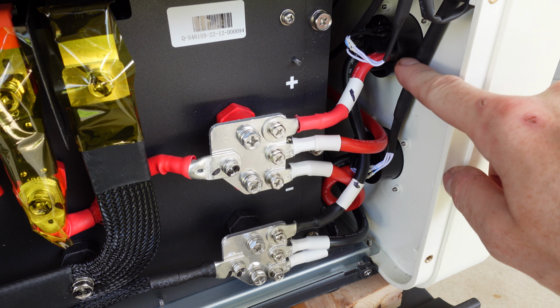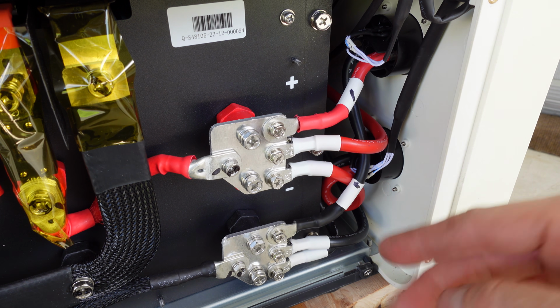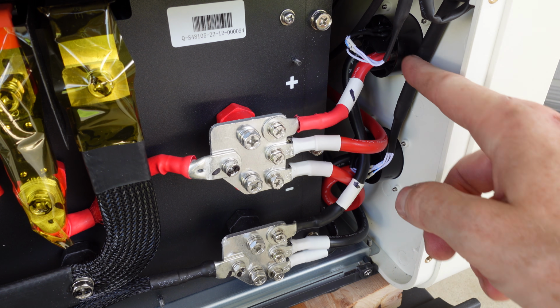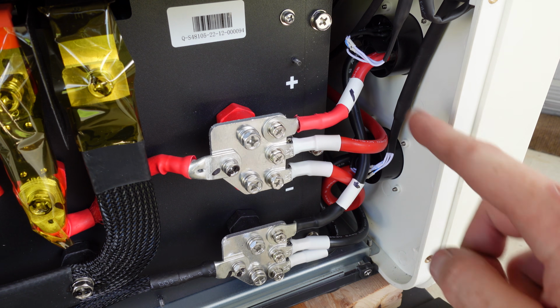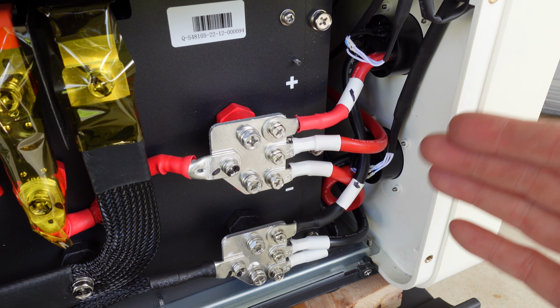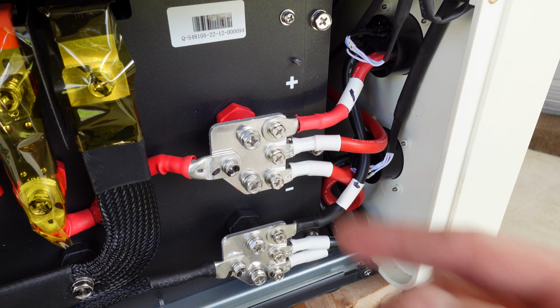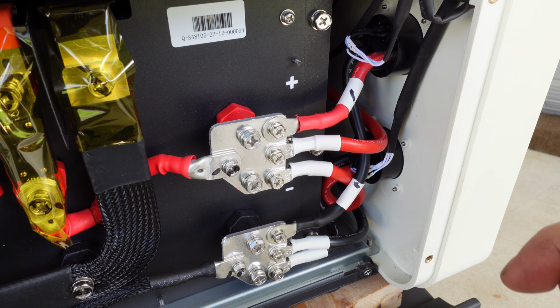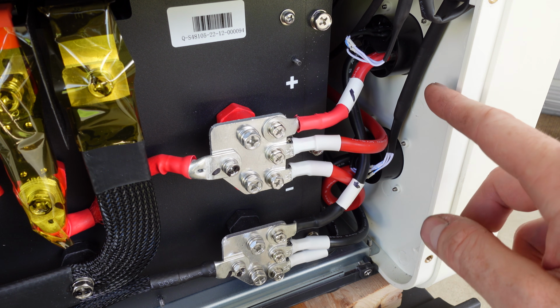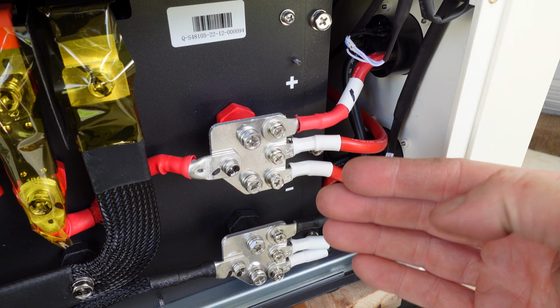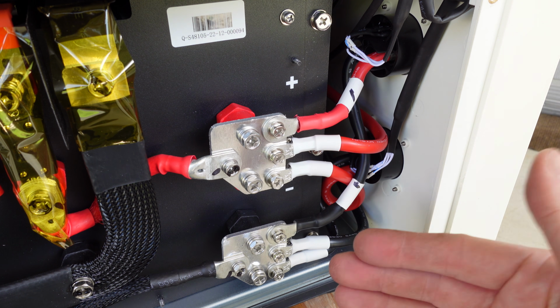This is why I noted you'll want to connect that battery parallel cable if you're using multiple of these inverters, because all that's doing is connecting all the batteries in parallel. There's nothing between these units other than the BMS operating on this battery itself. Everything connected to those battery terminals is simply dumped into the main battery connection point, which is this positive and negative bus bar.